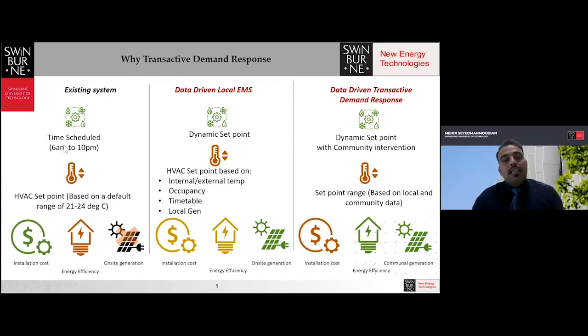In the existing building, both of these buildings, and most of the buildings we have, used time-scheduled set points. During the day, they had user compliance assurance, making sure that at a specific time the temperature set points were between 21 to 24 degrees centigrade. But there was a lack of receiving closed loop signal from the zoning. So we had some zones where, based on the semester schedule, we didn't have any activities, but the HVAC system was still operating when it didn't need to.